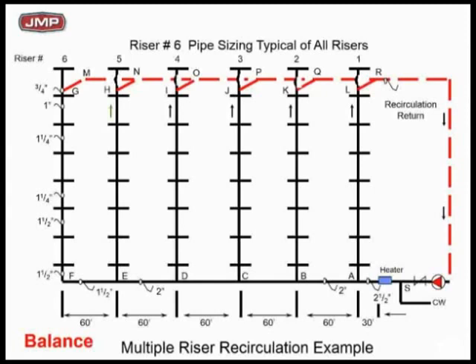With direct return and no balancing, if you moved out to the left to risers 3, 4, 5, and 6, the people on riser 6 in the morning could not get hot water — it took a long, long time. The poor person on riser 6 in the top room was the last person in the hotel to get hot water.